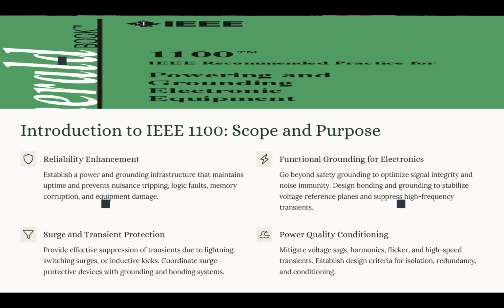Now, we have some disturbances when it comes to the power supplies. One would be the surge. It's like a transient from lightning, switching surges, or inductive load switching, and they can damage sensitive electronics or even cause errors in their function. Now, IEEE 1100 actually recommends using a surge protective device in our system, so we can properly coordinate those surge protections with the grounding system.